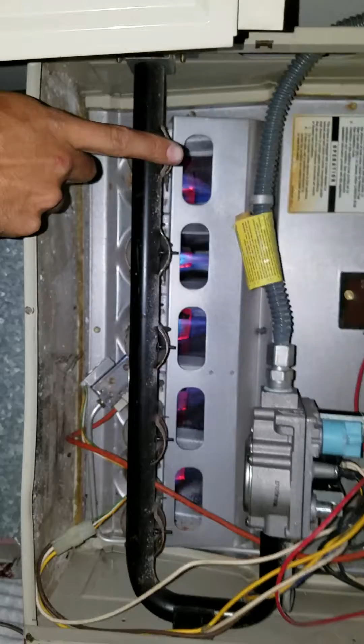Then if the flames stay lit for, let's just say 5 seconds and turn off, you want to take a look at your flame sensor, because the newer furnaces now, they've got a little flame sensor stick over here, and a hot surface igniter over here. So you're going to see this guy glow red, then you're going to see the flames, and if that only stays lit for like 5 seconds and turns off, your flame sensor over here, you want to take it out and clean it with a little bit of sandpaper. But that's when you get tools and stuff.